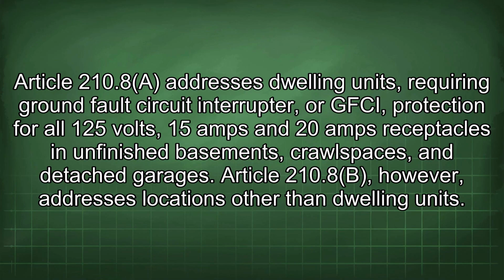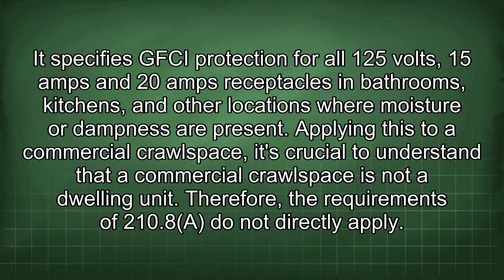Article 210.8 addresses dwelling units requiring ground fault circuit interrupter, or GFCI, protection for all 125 volts, 15 amps and 20 amps receptacles in unfinished basements, crawlspaces, and detached garages. Article 210.8(B), however, addresses locations other than dwelling units. It specifies GFCI protection for all 125 volts, 15 amps and 20 amps receptacles in bathrooms, kitchens, and other locations where moisture or dampness are present.